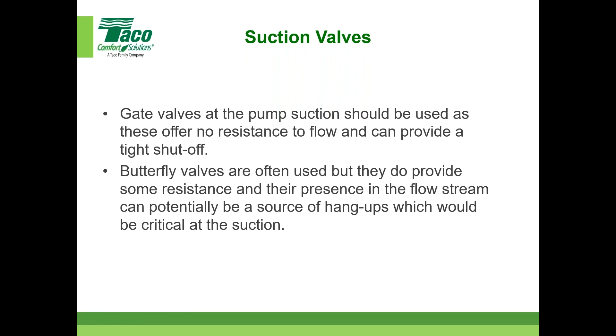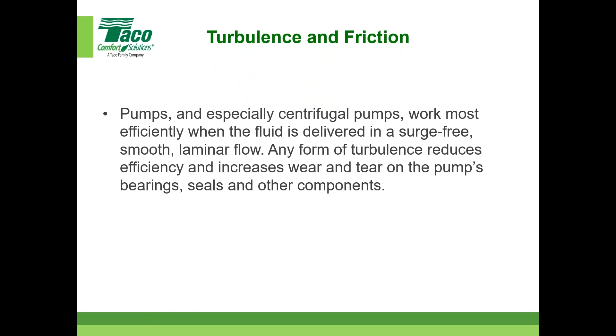These centrifugal pumps, I can't say it enough, really work better with surge-free, laminar, smooth flow going in. Try to reduce as much turbulence as you can, and it helps the life of the bearings, seals, and other components of the pump.